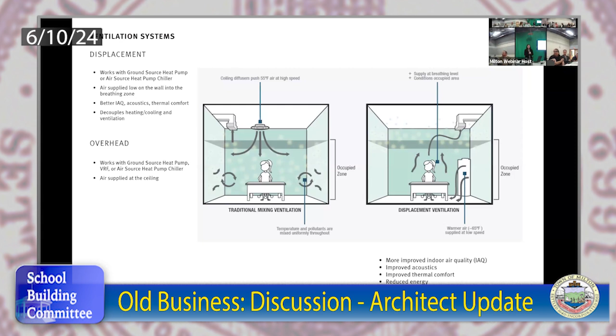Can you speak on the ability to cool though? Because the dehumidification system, in my experience, cannot cool to the extent that a more traditional HVAC or VRF system can. And in the first one, the chiller pump, whatever - can you talk about, between those three, what is the actual cooling effect within the spaces?